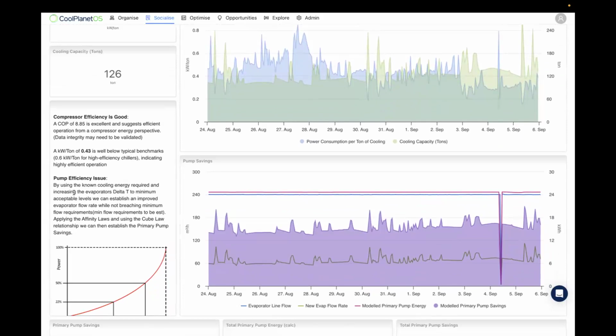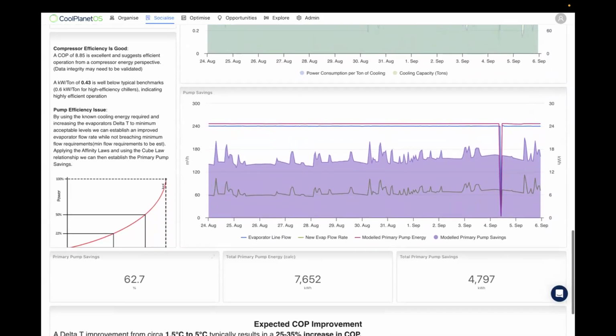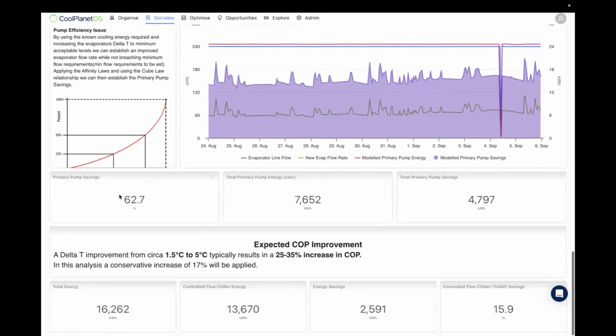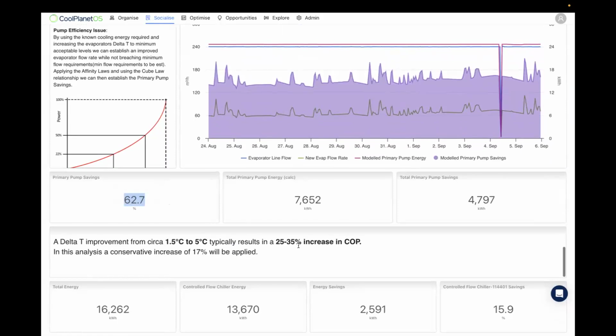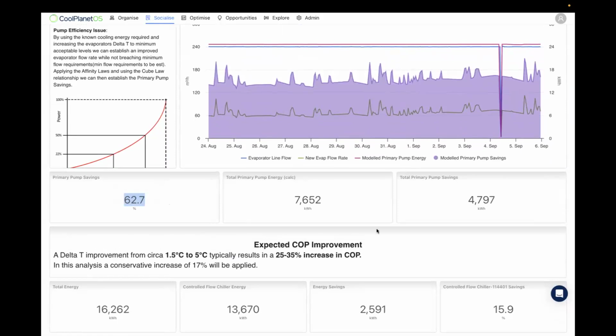So in this case, it's looking at the pump feeding the evaporator and how it's being controlled. It's using things like the affinity laws, and it's applying the cube law relationship to model out how, if we increased or optimized the control on this particular pump, that would affect the overall energy consumption.